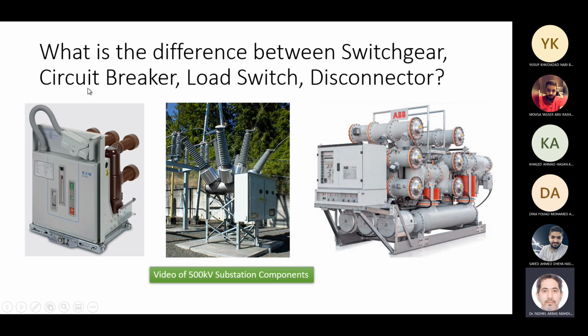However, a switchgear could be a combination of a circuit breaker and a disconnector. It could have an earth switch, metering devices, and protection devices. There are different types of switchgears, but it is a combination of different devices integrated together for the purpose of control, protection, and isolation at the same time. So it has protection devices, a control panel, CTs, VTs, a breaker, and disconnectors in it. I'll come to this later.